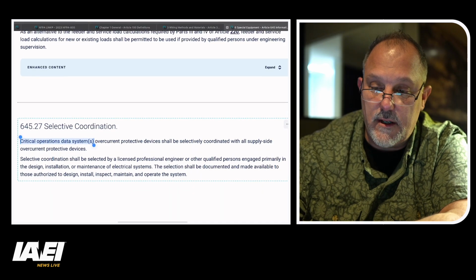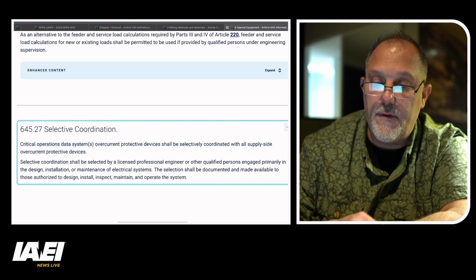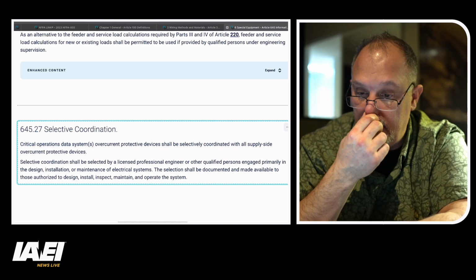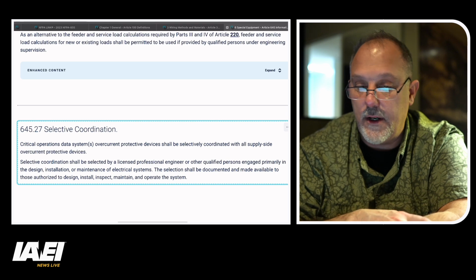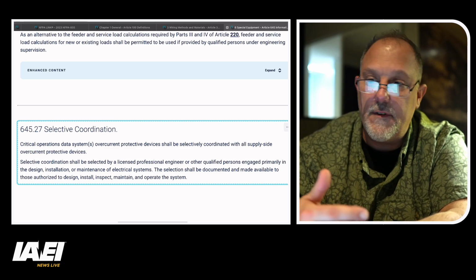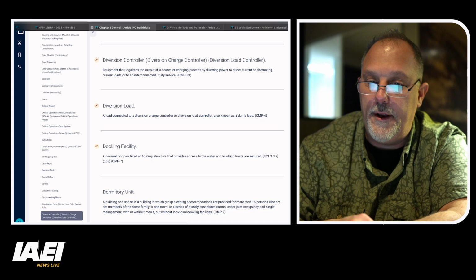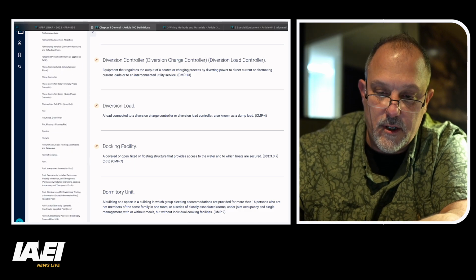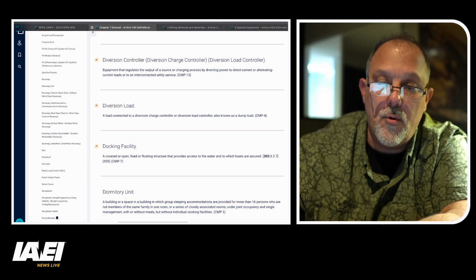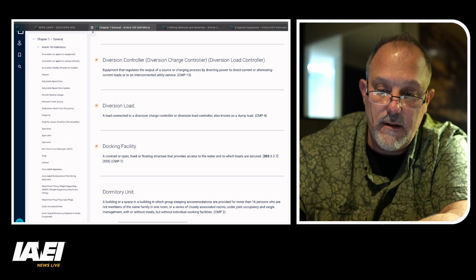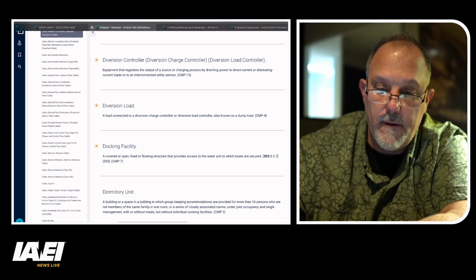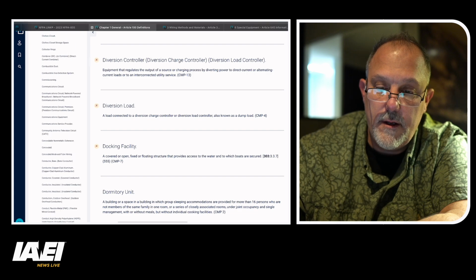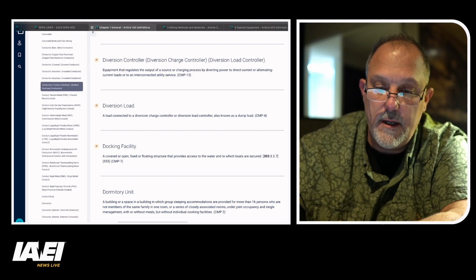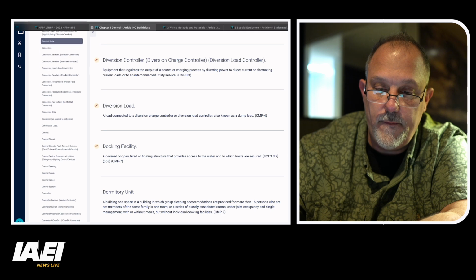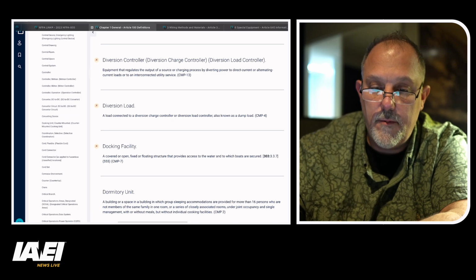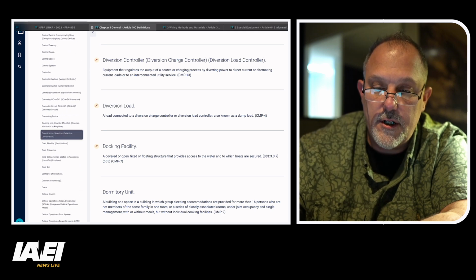So selective coordination is required for these. Now that would be critical operations data systems. Overcurrent protective devices shall be selectively coordinated. And we know what the defined term of selectively coordinated is if we go back to chapter 1 and run down to selective coordination, or coordination selective. I think it's a C. Coordination selective.